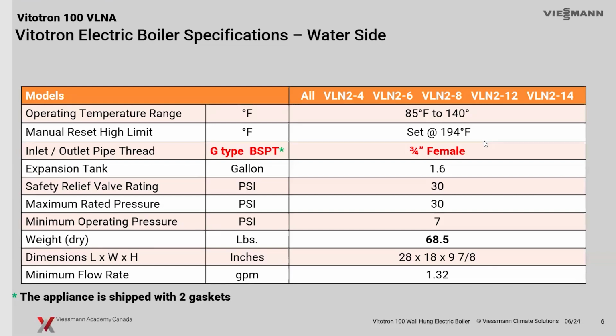On the water side of the system, we see maximum temperature. We call it a low temperature boiler that limits at 140 as far as an operating temperature. That covers a vast amount of our hydronic applications these days, especially typically sizing now for condensing applications and boilers. A lot of designers have gotten used to those low temperature designs. A lot of retrofit applications, if you're going from a gas boiler to an electric one, and a lot of municipalities are banning putting in fossil fuel equipment and want you to go to something electric. This is an option for you to go there. And of course, a lot of the systems we're replacing are low temperature. Just keep in mind that we're up to about 140 Fahrenheit, 60 C, as our maximum supply temperature for the operating side of it.